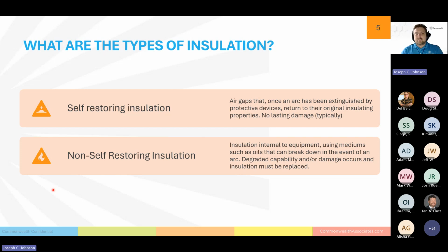Non-self-restoring insulation is the insulation that can be more on the inside, not necessarily inside of devices, but oil immersed transformers, breakers, inside of the actual breaker device. There's gases and there's oils in these pieces of equipment. And if there's an arc inside of that, well, those aren't readily replaced by more oil around them necessarily. You get a degradation of that medium. And so best case, eventually you need to replace it, maybe even after one event, maybe you can survive a couple events. Worst case, you have damage internally to the equipment and a severe degradation of the protection of that insulating medium.